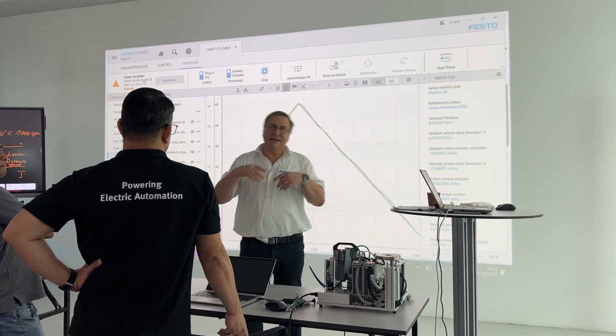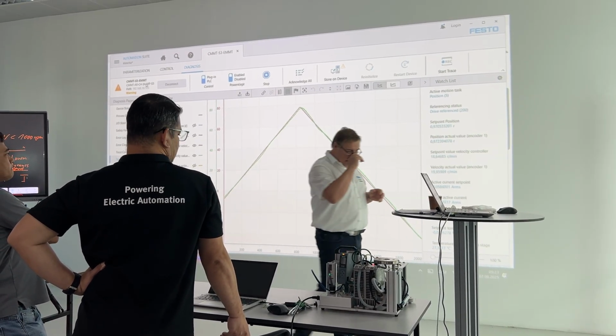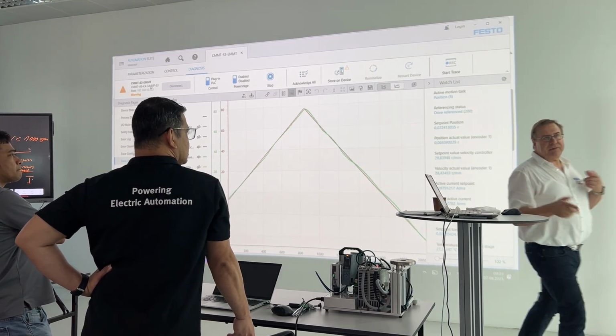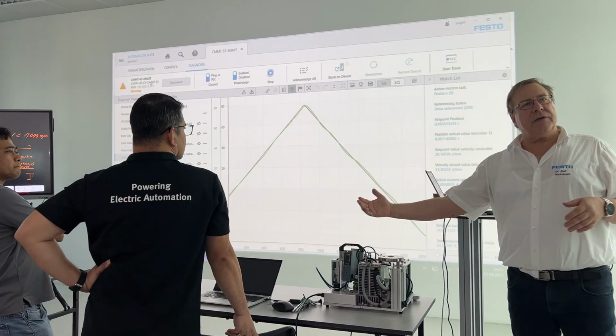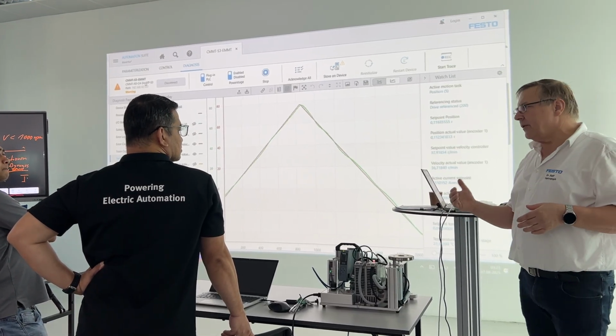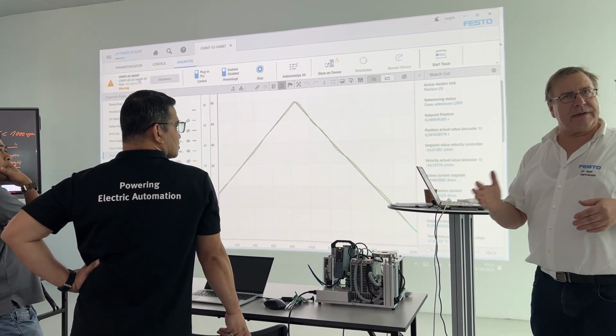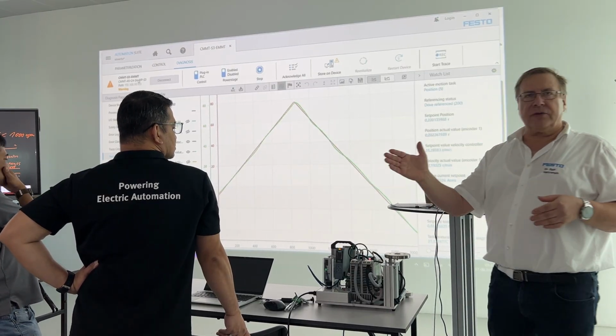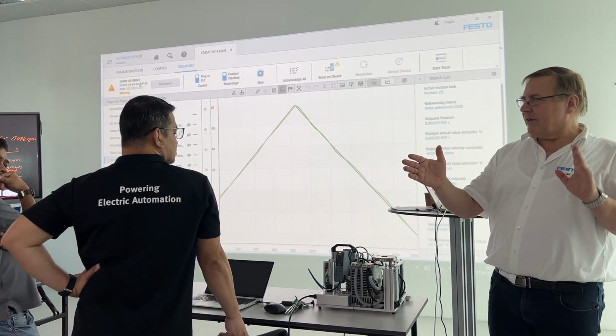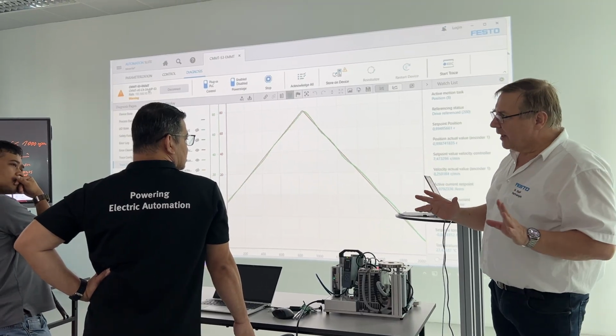And more or less, in this interpretation, I'm doing the same. I enhance my amplification first until I see the system is starting to get unstable, then reduce to 0.8 or 0.75 of this parameter. Then I make the system faster until I come to the unstable position, and go back to 0.8, or 0.75, of the original one. And in most cases it will work.